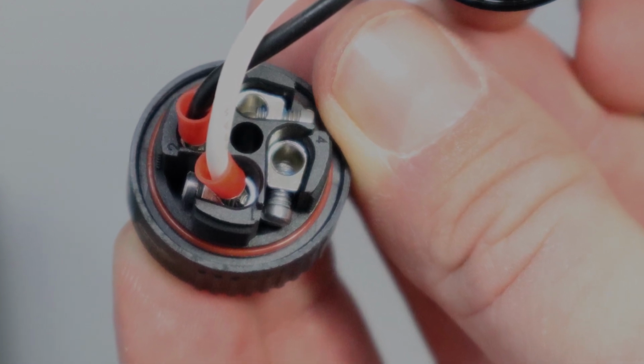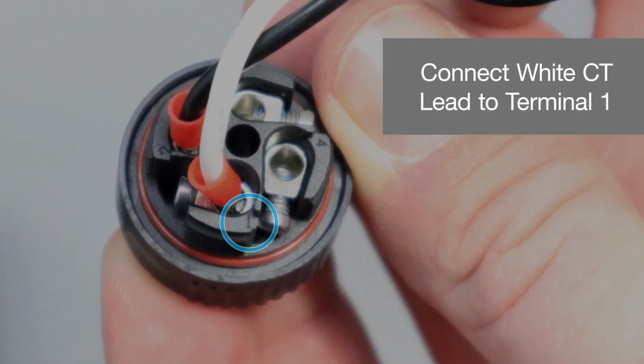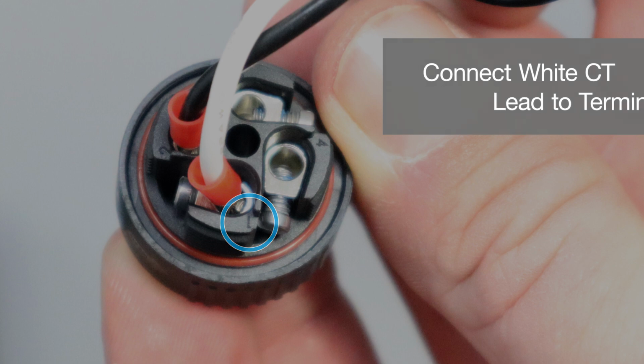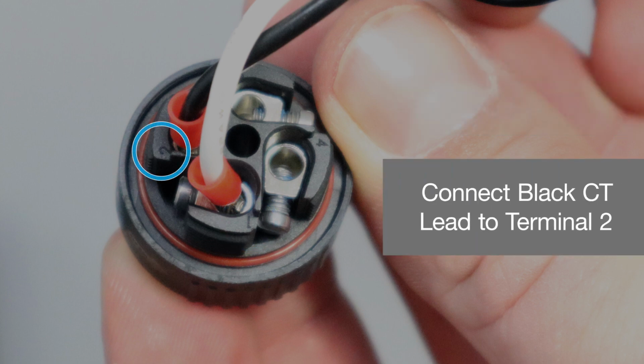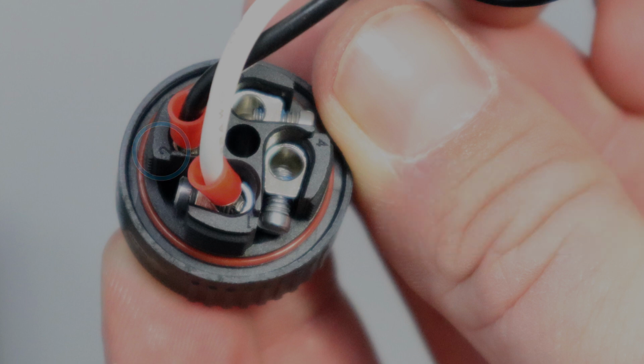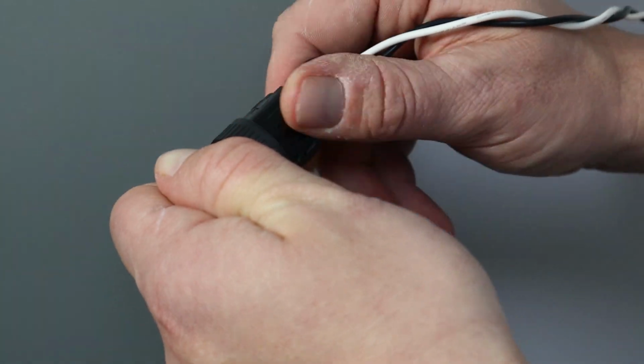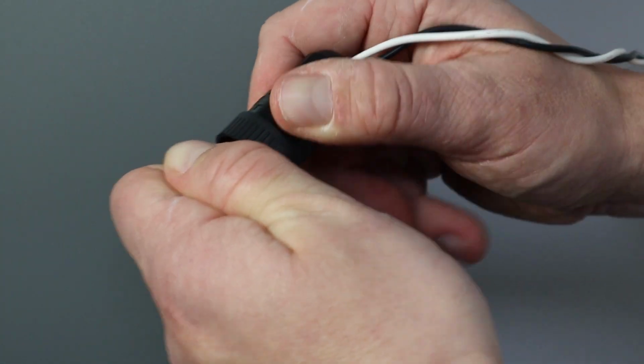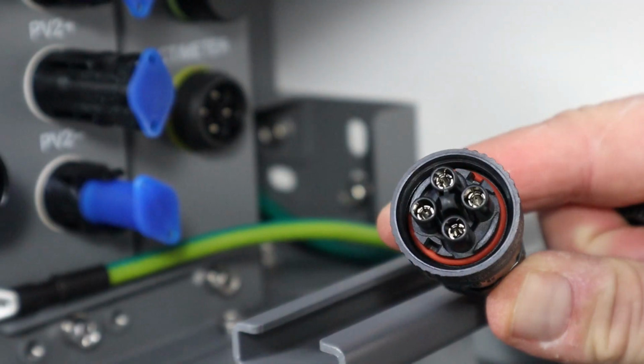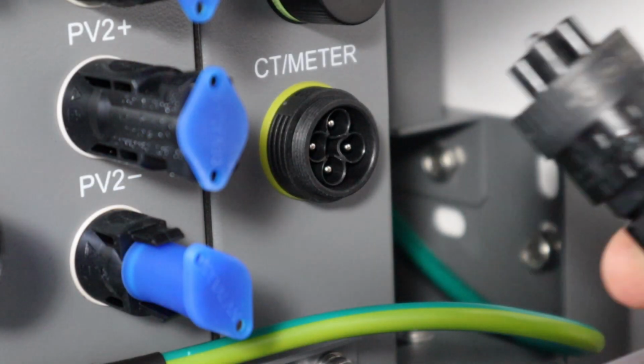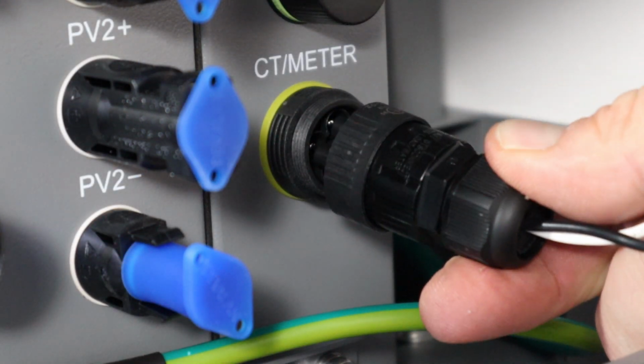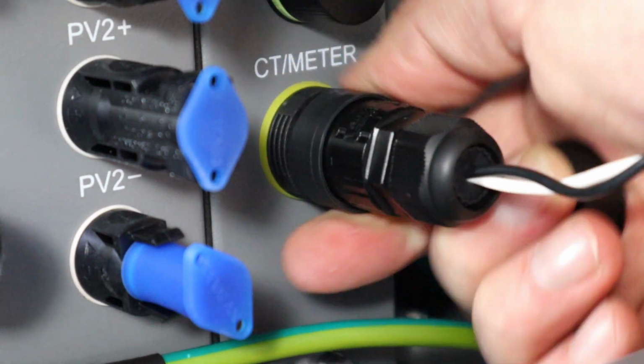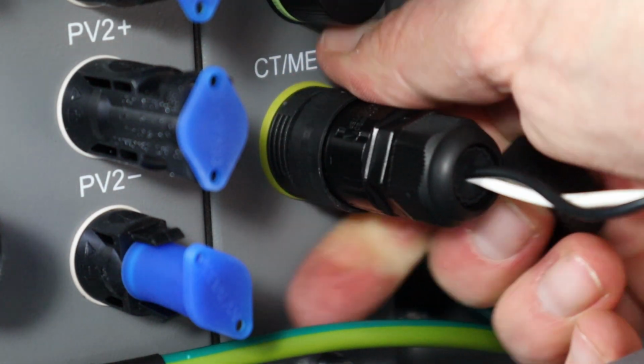For energy flow measuring using a current transformer, connect the positive S1 white lead from the CT to terminal 1 of the CT meter plug. Then connect the negative S2 black CT lead to terminal 2. Screw down the plug housing and tighten down the cable grommet. Check the plug orientation and insert into the CT meter socket, ensuring it is fully seated and the retaining ring is firmly screwed into place.